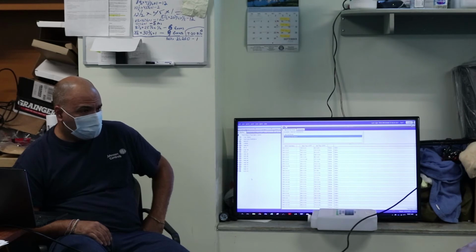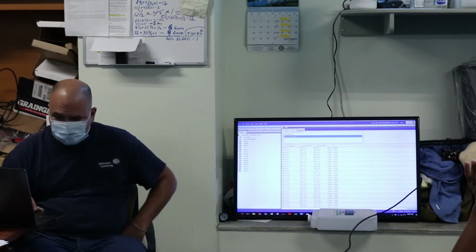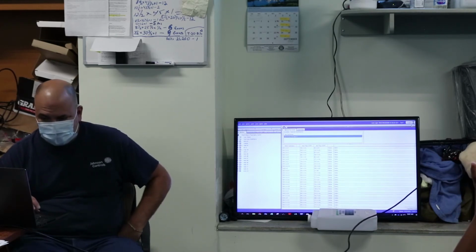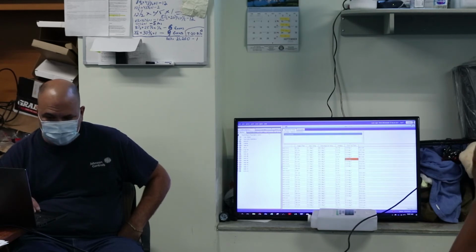In NRB, yeah, they're all set about 60% outside. Exactly. So even in the winter time, you're going to be preheating. Yeah, exactly. So now we could just have a constant set point. We know the outside air temp is going to stay at this point. We create a temperature of supply of literally 72, and then we have our heating set at a constant.